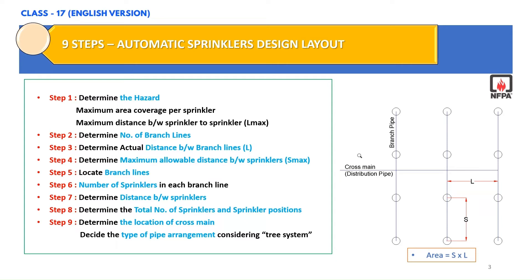Step 1: We shall determine the hazard occupancy classification, maximum area coverage per sprinkler, and maximum distance between sprinklers (Lmax), based on the hazard occupancy classification. Step 2: We shall determine the number of branch lines. Step 3: We shall determine the actual distance between branch lines, denoted by L. Step 4: We will determine the maximum allowable distance between sprinklers, denoted by Smax. Step 5: We shall locate the branch lines in the design area. Step 6: We shall calculate the number of sprinklers in each branch line. Step 7: We will determine the distance between sprinklers. Step 8: We shall determine the total number of sprinklers and place them in the complete office area. Step 9: We shall determine the location of the cross main and decide the type of pipe arrangement, considering a tree system.